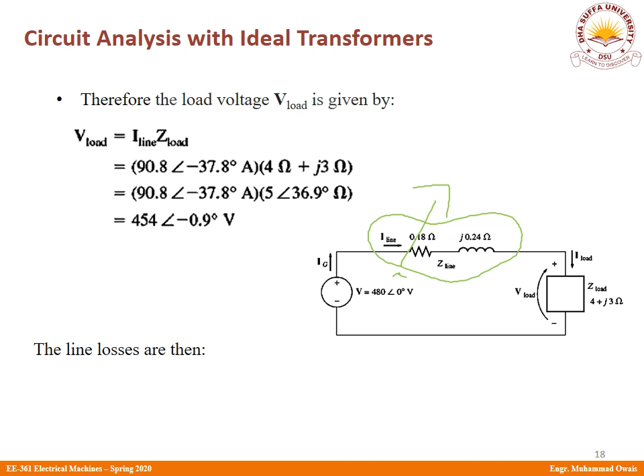Now how do I find the transmission line losses? The transmission line losses are nothing but the I squared R losses. When we talk about I squared R losses, we consider only the resistance of the transmission line, 0.18, using the basic relationship of line losses: I squared into R line. I line is the magnitude of the line current, which was 90.8 as we solved in the previous slide, and the resistance in the line is 0.18 ohm. Once you solve this, you get the value of 1484 watts.